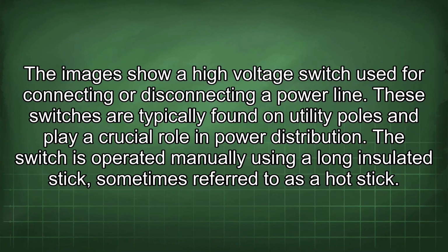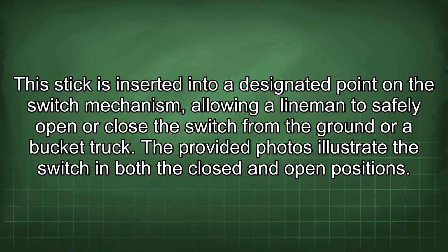The images show a high voltage switch used for connecting or disconnecting a power line. These switches are typically found on utility poles and play a crucial role in power distribution. The switch is operated manually using a long insulated stick, sometimes referred to as a hot stick. This stick is inserted into a designated point on the switch mechanism, allowing a lineman to safely open or close the switch from the ground or a bucket truck.